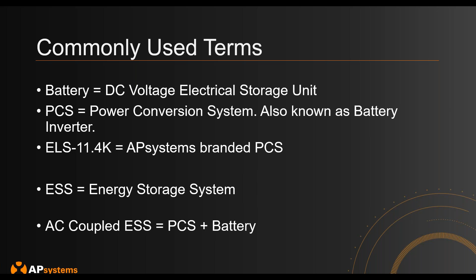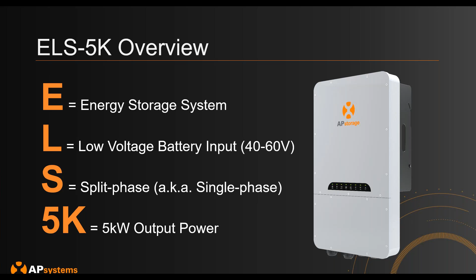As a first generation example, this is the first generation APstorage product we've sold already in Canada, the US, and around the world. It's called the ELS 5K. The E stands for energy storage system, L stands for low voltage battery input, typically 40 to 60 volts, S stands for split phase or single phase, and 5K refers to the output power the system is capable of backing up.